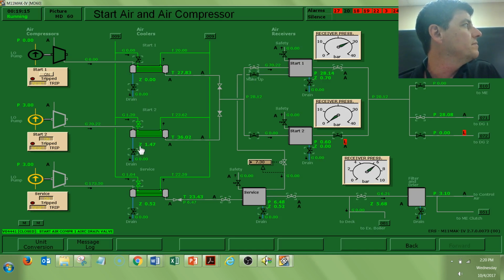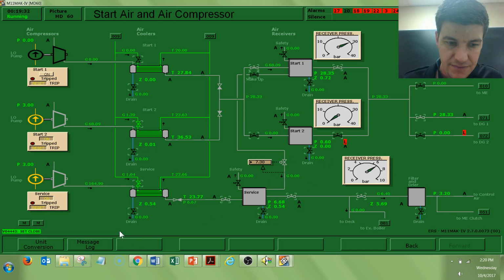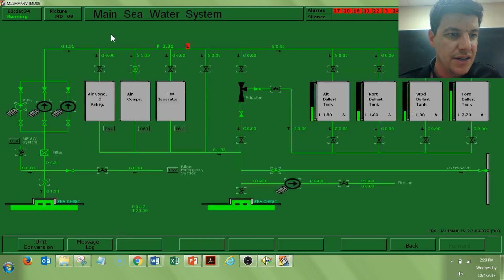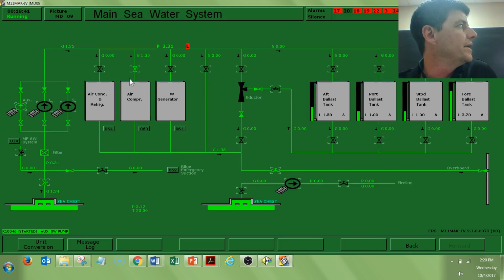Drains should only be used sort of sparingly. So for instance here I've got a bit of water. I open it up for a few seconds to drain out any water and then that would be closed. So I'm not using drains. So basically a normal operation, all would be closed. On the cooling water side, again you've got a pathway. Auxiliary pump is all I need at this point for my air compressors and flowing through to overboard.